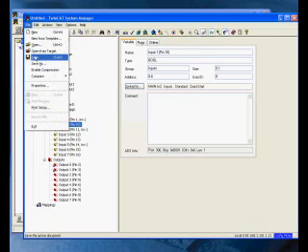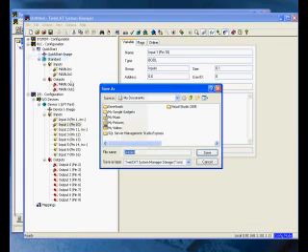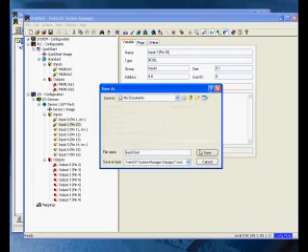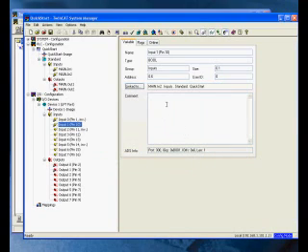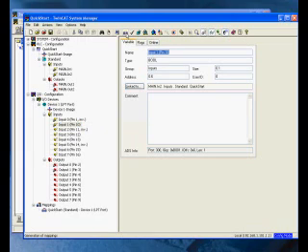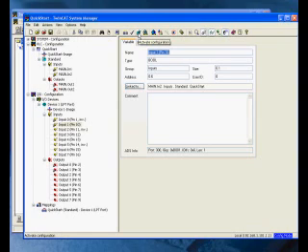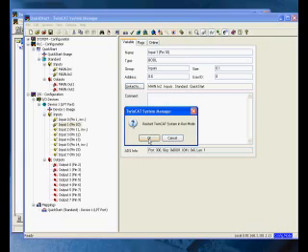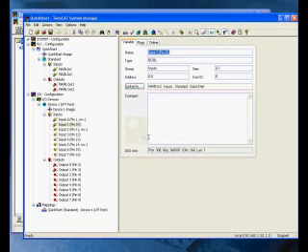Now let's save the project, which is the system manager file. We'll give mine the name, save it in my documents also. So now we've linked that to hardware so we're going to generate mappings. I'm going to check it, verify everything and then I'm going to activate my configuration. So now I'm basically saying the addresses I defined in my PLC program are going to be linked to physical IO and that's what the mapping is for.